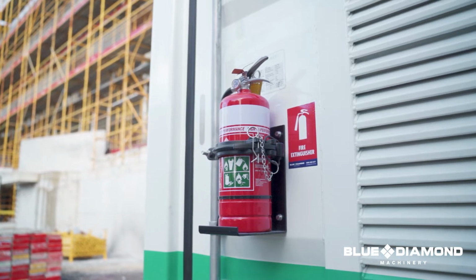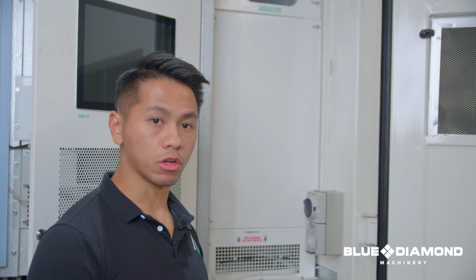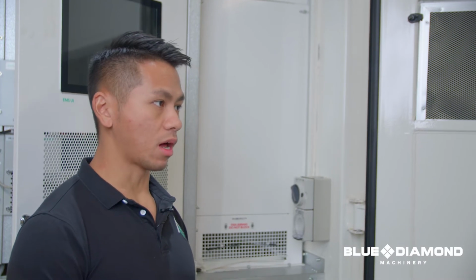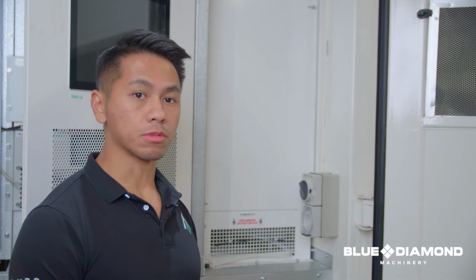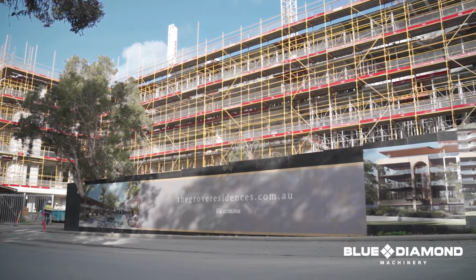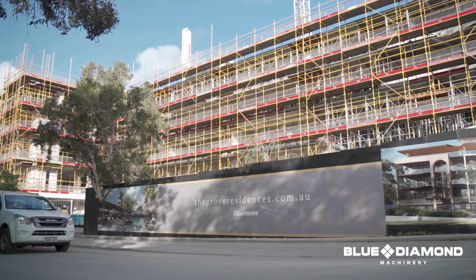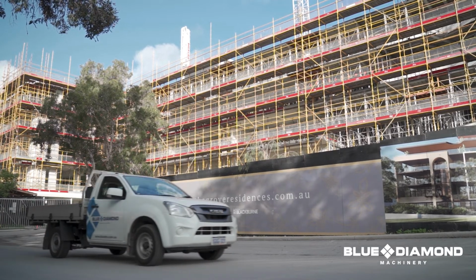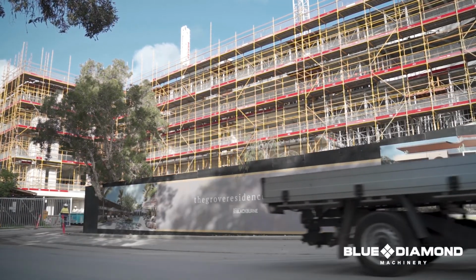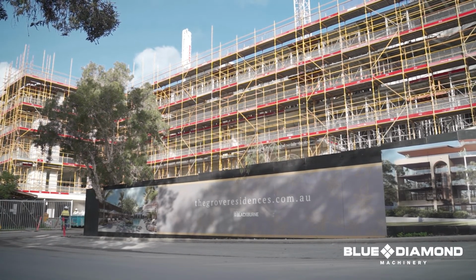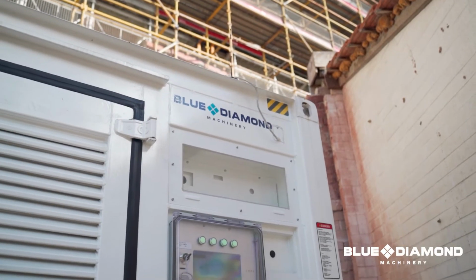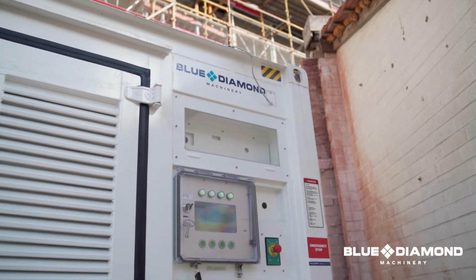In construction sites, there are tendencies of fires to happen, especially with lithium-ion batteries when they overheat. Studies have shown that without a proper battery management system and without a proper fire suppression system, you would have fires that could occur. So we fit a control panel here that talks to smoke sensors and heat sensors placed strategically across the room in order to sense if there is a hint of fire and to immediately and automatically deploy FM200 extinguishant to put out that fire.